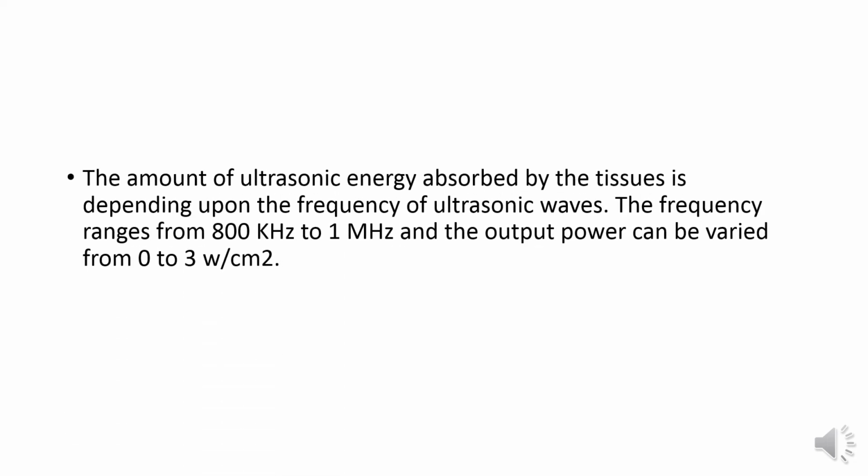The amount of ultrasonic energy absorbed by the tissues depends upon the frequency of the ultrasonic waves. The frequency ranges from 800 kHz to 1 MHz and the output power is varied from 0 to 3 watts per centimeter square.